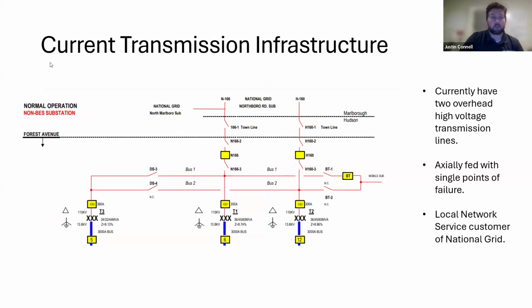For those of you who are electrical engineers, I am one, but not a very good one. This is a one-line diagram. You don't need to study or understand the drawing, but in the top part we have two overhead high voltage transmission lines that come in from National Grid. One is the N166, and one is the H166 line. Those come into the main Hudson substation, where we have breakers that can isolate both lines, and on our side we also have a bus tie breaker. So we have capacity from both lines, and the ability to backfeed in the event of an outage of one of them and still maintain system power.